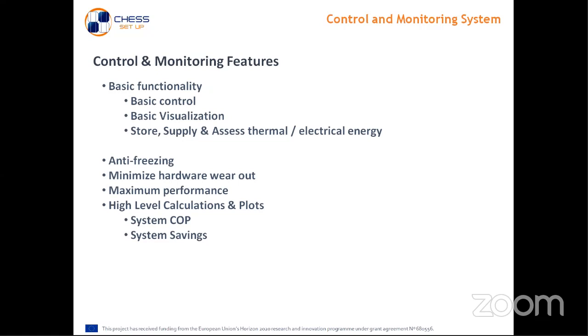We also minimize hardware wear out. For example, in critical parts of the circuits there are twin water pumps, a main one and a backup one, in case the main one fails. The system automatically alternates the usage of the pumps to keep them equally used, so that when we need the backup one, it doesn't fail because it's rusty or stuck from not being used for a long period of time.